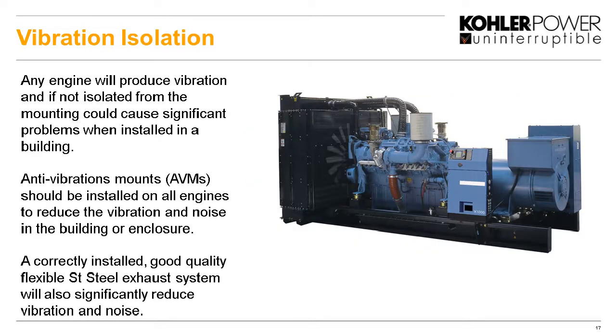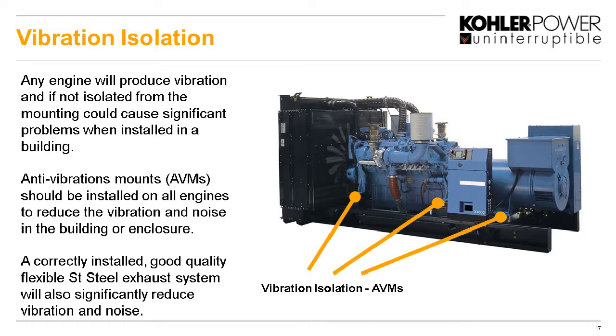So another thing I mentioned is vibration. Engines vibrate a lot, as we know, especially when they're put into buildings. We can have significant problems with vibration throughout. So we have to make sure that we put anti-vibration mounts onto the generator itself. And these are mounted beneath the engine and the alternator. And these are rubber mounts. It's very similar to what we have in vehicles, that allow the vibration not to be transmitted through to the container or through to the building. Although obviously we're going to get a little bit, but we reduce that as much as possible.